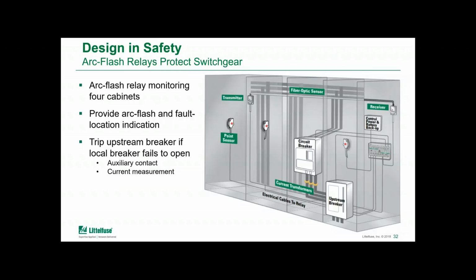So to show, for those not familiar, just so you can visualize how arc flash relays are put into equipment, in the switchgear picture here, you can see the arc flash relay is installed on the right-hand side of the cabinet, and there's 4 sections to the gear. And here it's utilizing 3 single-point sensors, one inside each cabinet. Those are the small white boxes there, as well as a fiber optic sensor that can be installed along the bus bar in the back of the equipment.